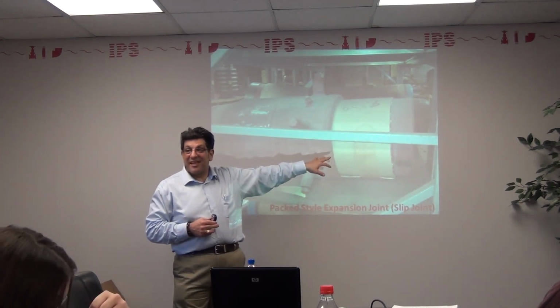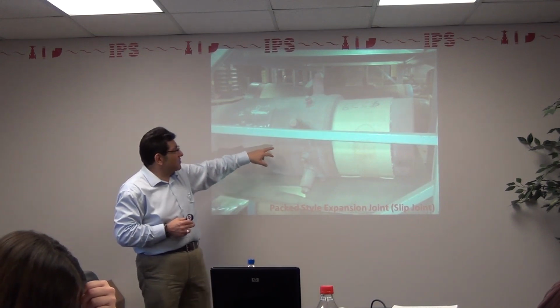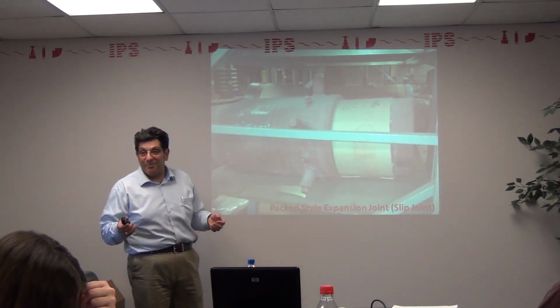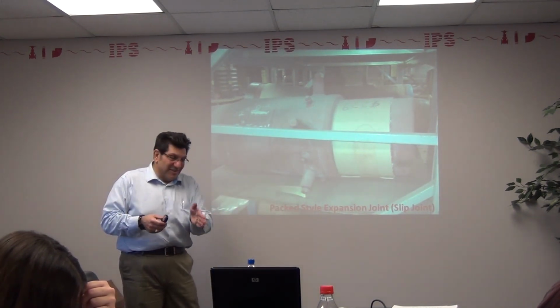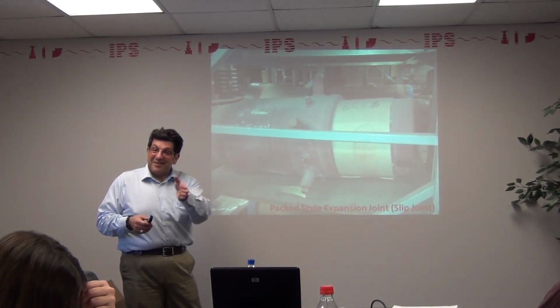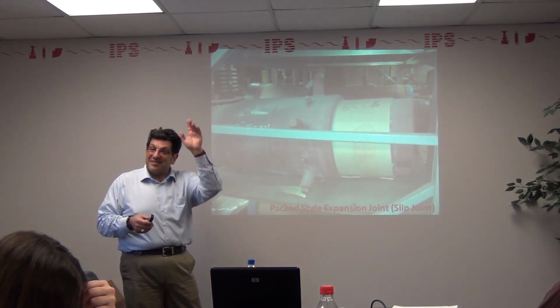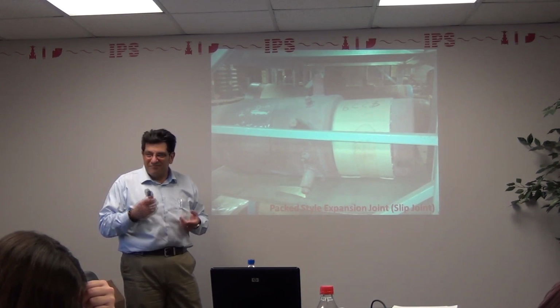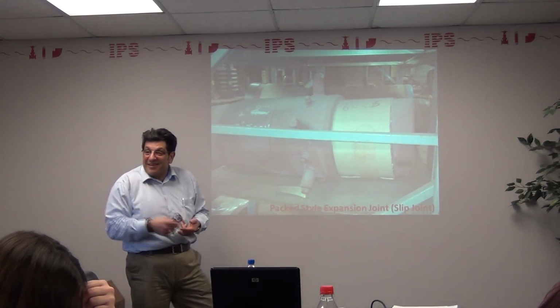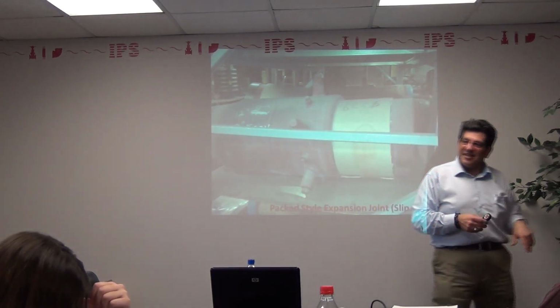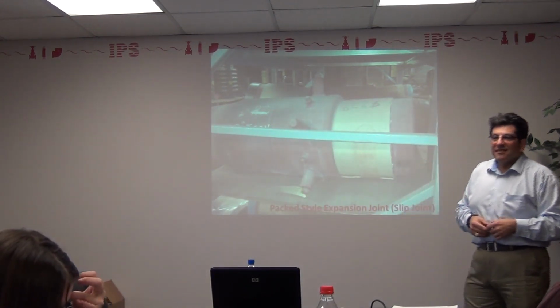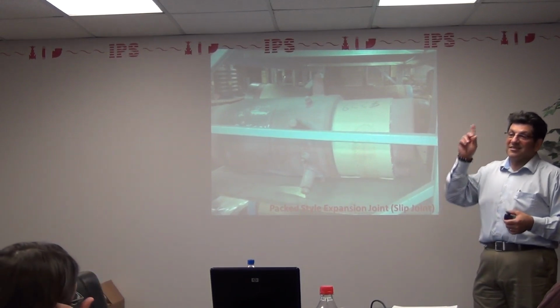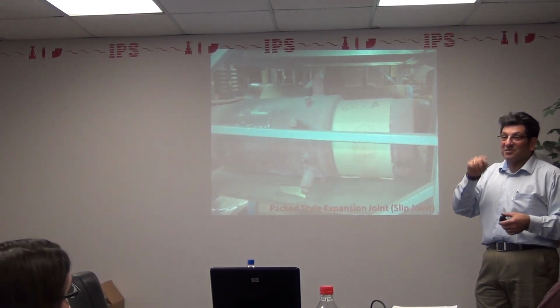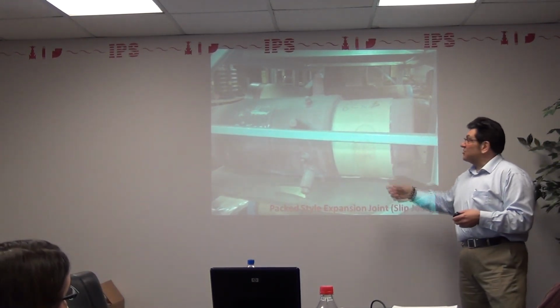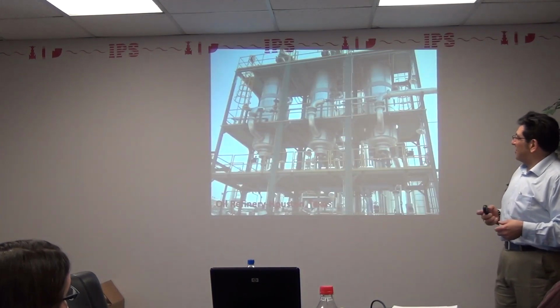Never. It's dangerous as heck, and they just don't do it. That's why on a college or hospital campus, when it's snowed, you can see right where the steam lines are, or see steam blowing up through the manholes. It's bad traps, your Watson McDaniel people will tell you about that, and it's these things leaking like a sieve. They're everywhere. And what's all that steam when it escapes? It's cash money, that's what it is. So again, you can replace all of those.